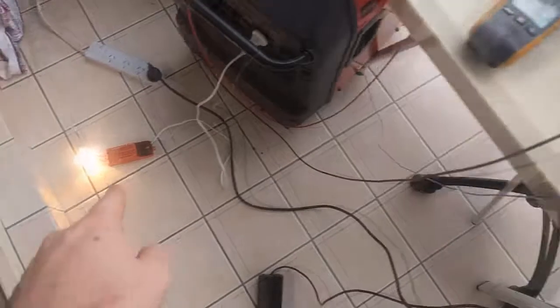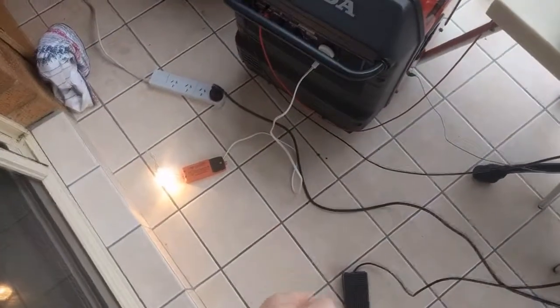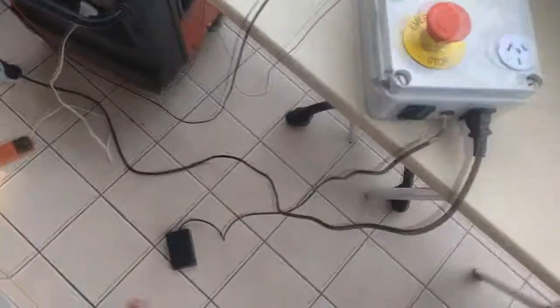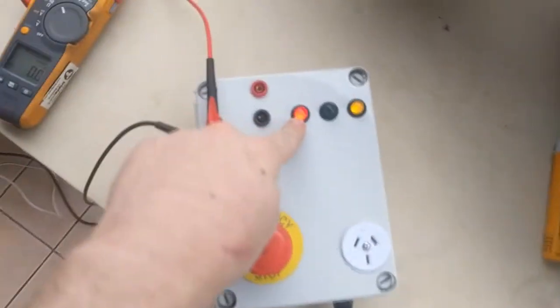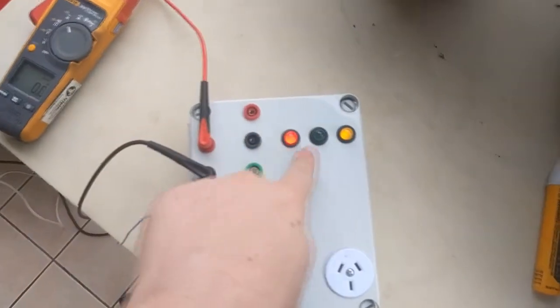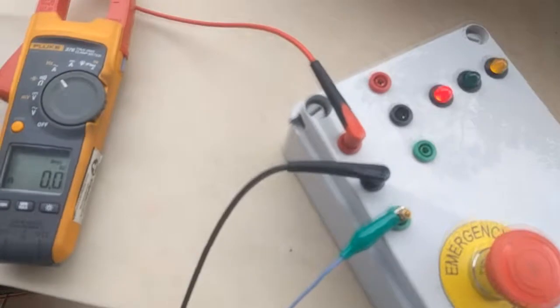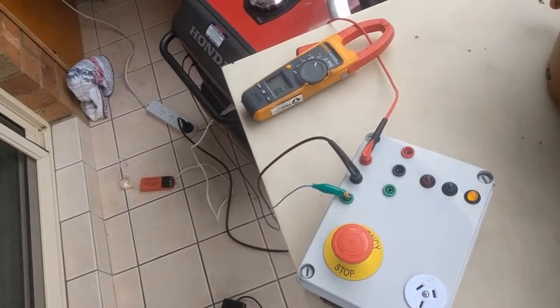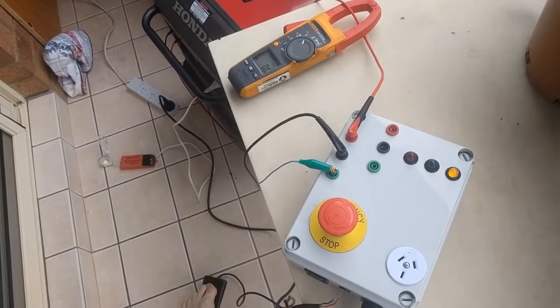I've just closed the interconnect now. I've still got power present because now that's on generator — the grid is cut from the generator. That's grid power going out, that's gen power.